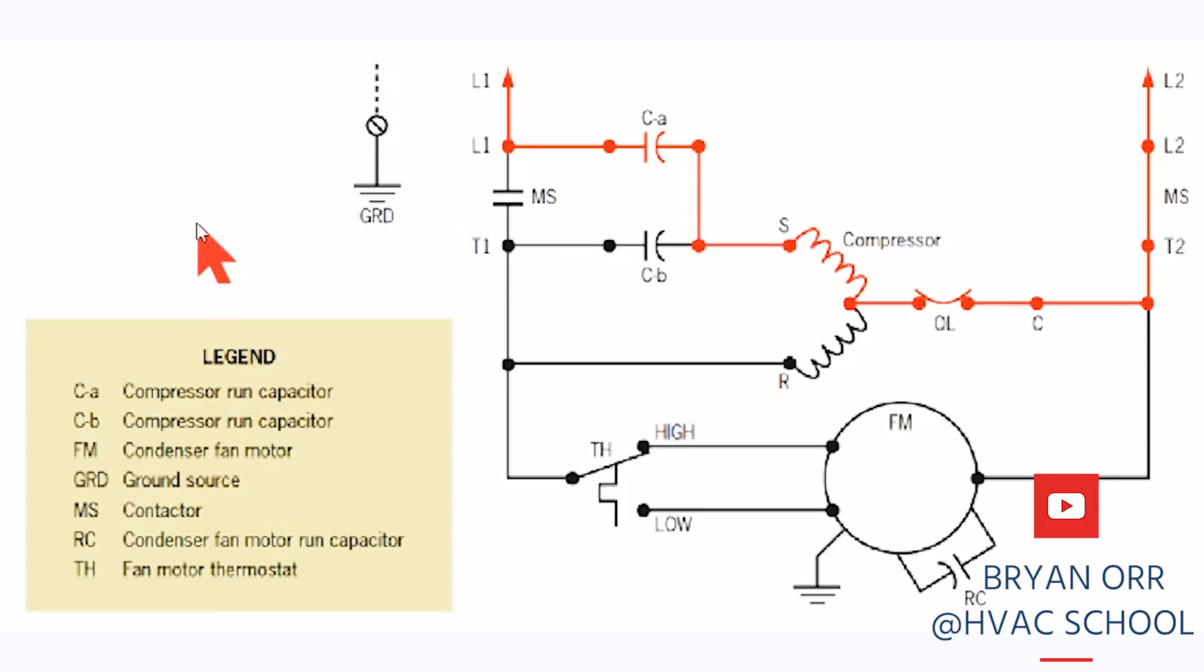This is an interesting case study - this type of crankcase heater configuration uses the compressor start winding as a heater to keep the compressor warm even on the off cycle, which can help prevent liquid refrigerant from migrating into the crankcase. That's the reason for a crankcase heater - to prevent liquid refrigerant from migrating to the crankcase.